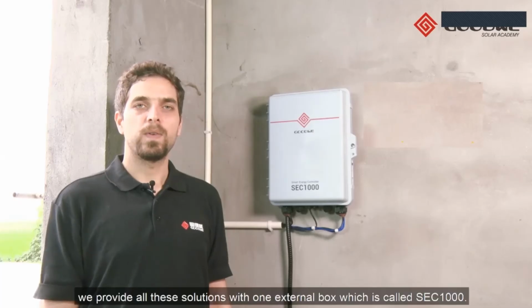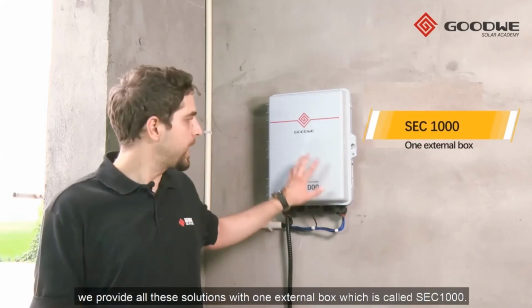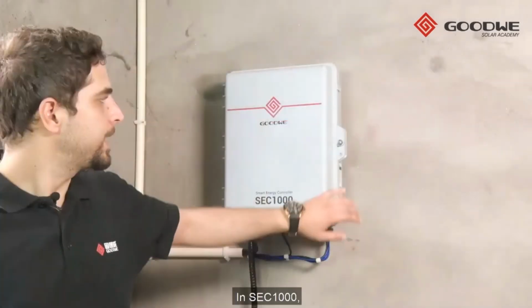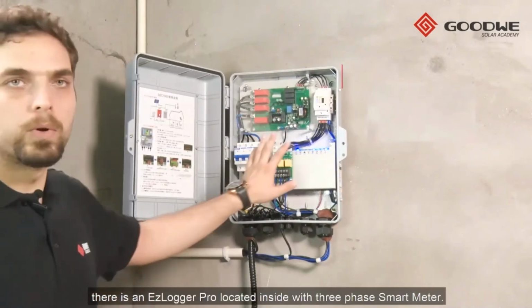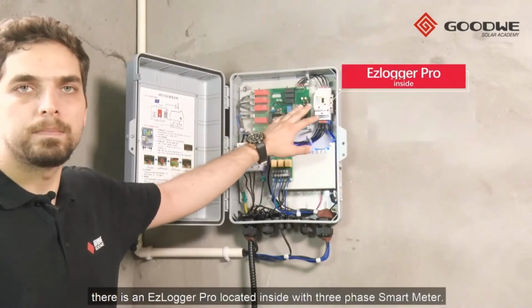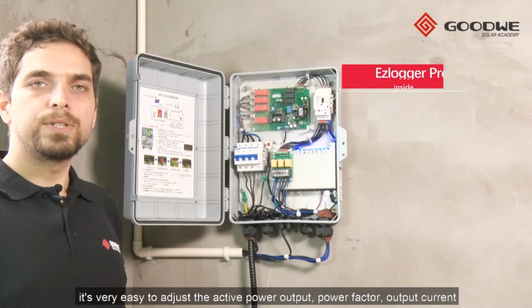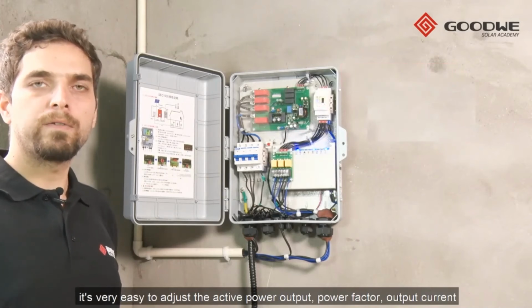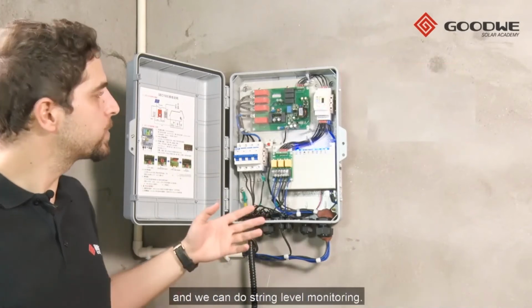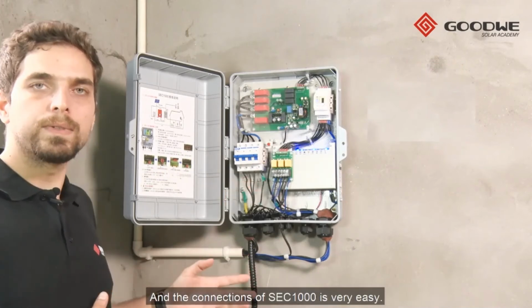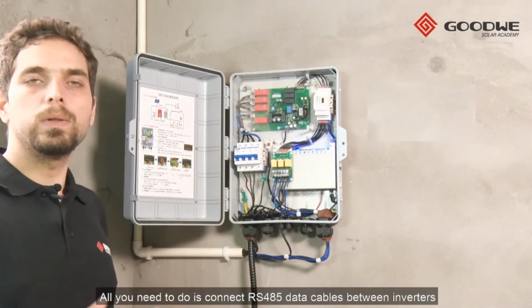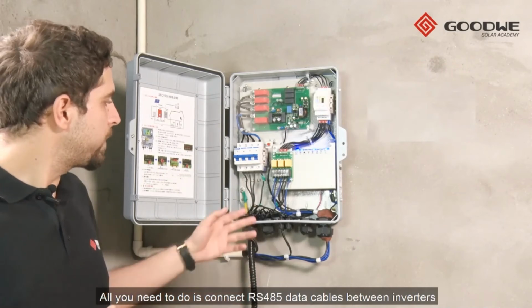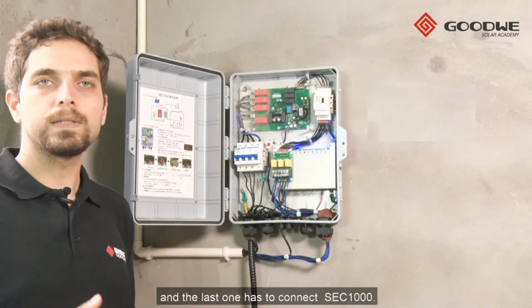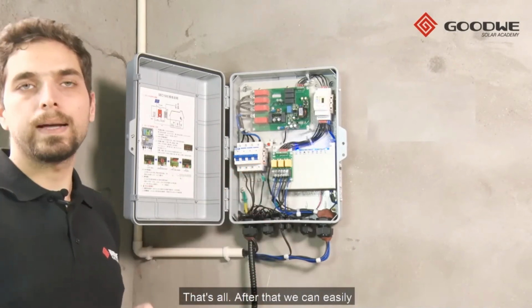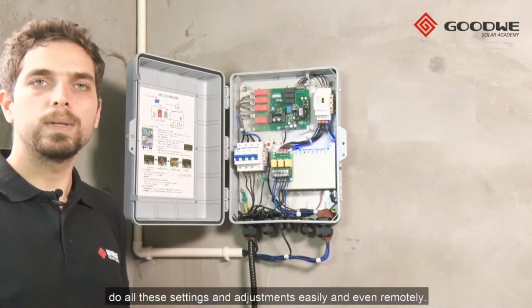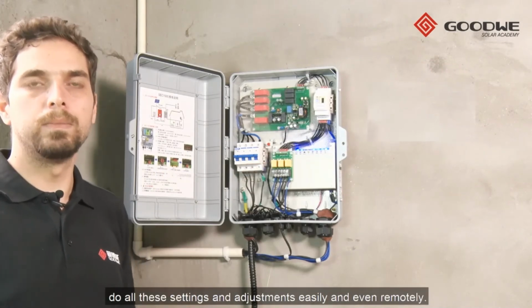Here in GoodWe, we provide all these solutions with one external box which is called SEC 1000. In SEC 1000, there is an EzLogger Pro located inside with a 3-phase smart meter. Thanks to it, it's very easy to adjust the active power output, power factor, output current, and we can do string level monitoring. And the connection of the SEC 1000 is very easy. All you need to do is connect RS485 data cables between inverters, and the last one has to connect to SEC 1000. That's all. After that, we can easily do all these settings and adjustments, even remotely.